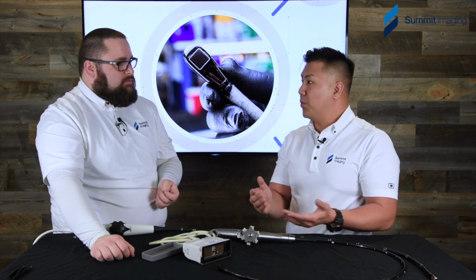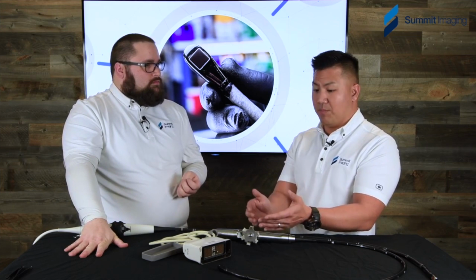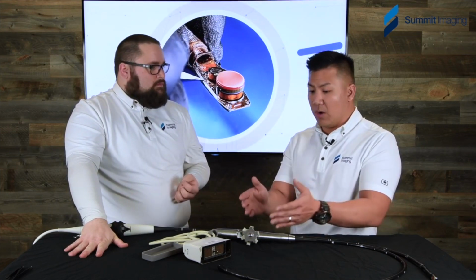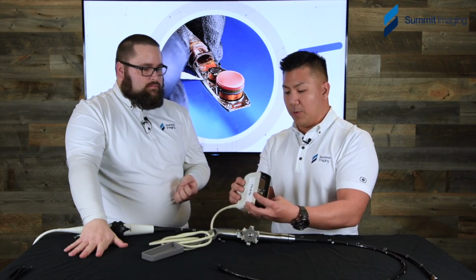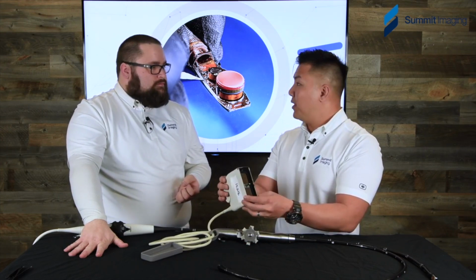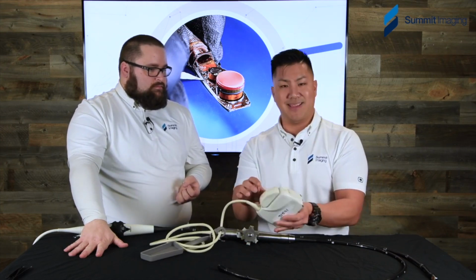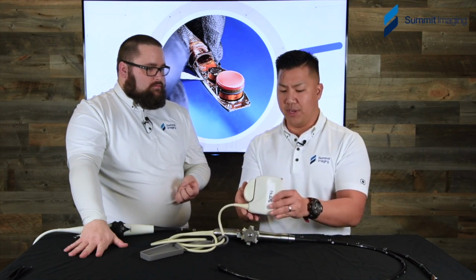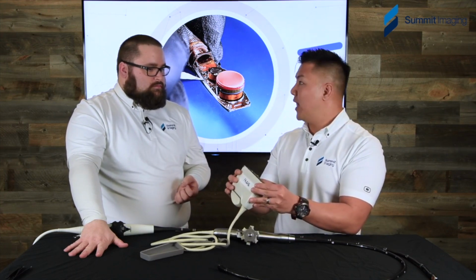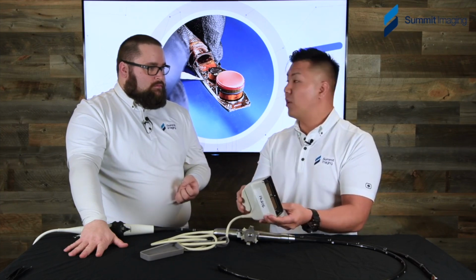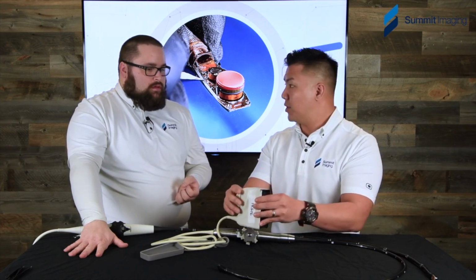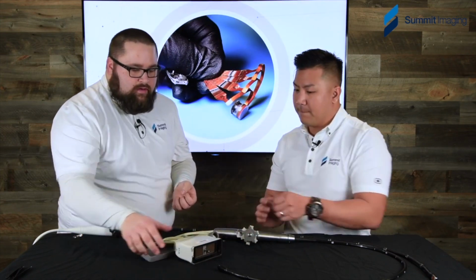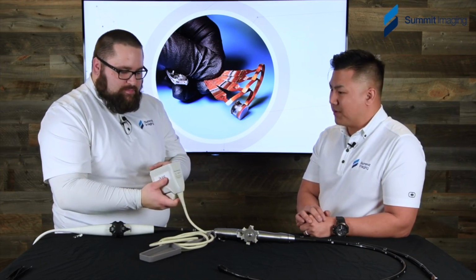And so that's one of the things that we inspect for every single time, to make sure that the correct OEM parts for these critical pieces are there. There are so many people out there that may misinterpret this as just a cosmetic can that holds it together and looks pretty. No, if you actually take a DMM and analyze this, it is a part of the ground circuit, and it is critical to the ground circuit. Yeah, and plastic is not even close, right? Not even close. No effort to be even partially close at that point.